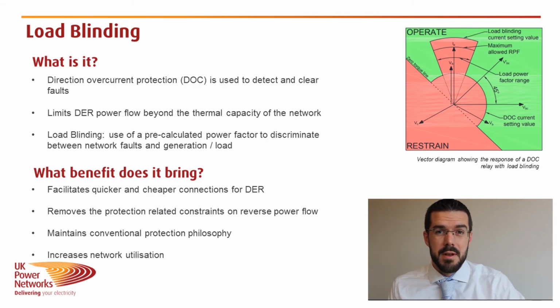This means that in many places on our network where there are reverse power flow constraints that are caused by directional overcurrent protection, we can replace the protection with modern relays with load blinding capability and enable more generation to connect more quickly at lower cost up to the thermal limit of the equipment.